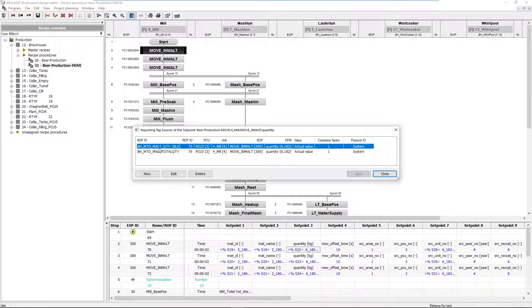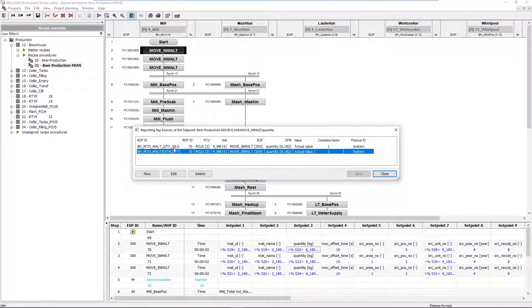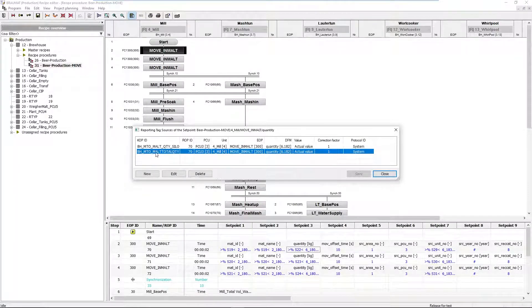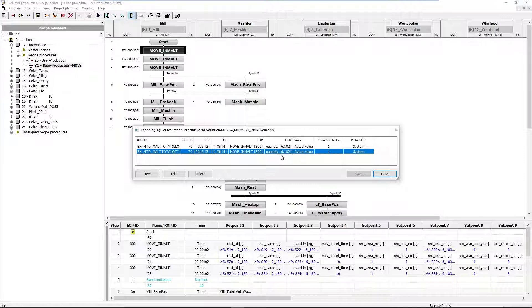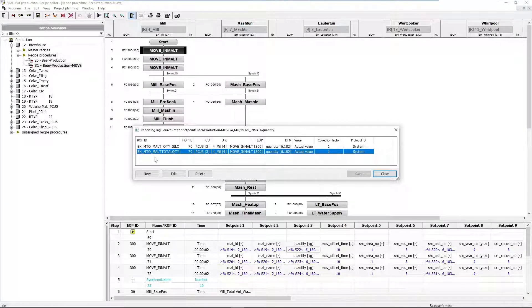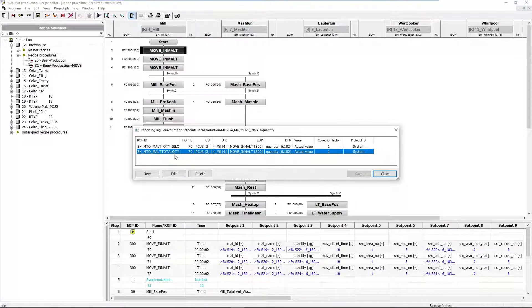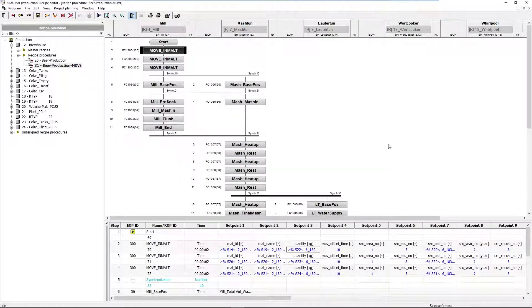That means I link the malt quantity twice. Once with the actual quantity of malt inside the silo, and then each time I identify this quantity, target value and actual value, within the project planning. I link it to the sum parameter and then the sum is automatically calculated during the step change. We will see this again in a moment.